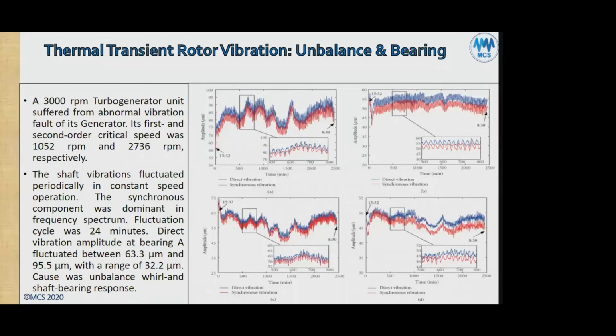Direct vibration amplitude at bearing A, the top 2 being bearing A, fluctuated between 63 micrometers and 95 micrometers, with a range of 32 micrometers delta. Now, when the machine was troubleshot, they first tried a balance to see if that helps the situation. Because is this thermal related? Yes, it is thermal related, and it's in the generator. So it's something in the rotor itself or interacting with the stator, because the stator is electrical also.